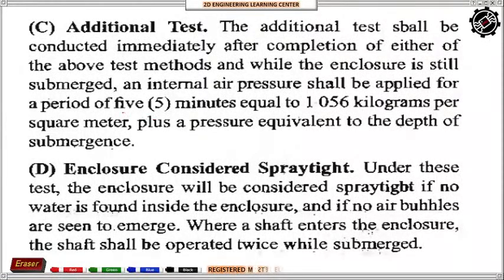The additional test must be done within 5 minutes, subjected to a pressure equal to 1056 kilograms per square meter. Likewise, it also has an enclosure spray tight. Under this test, the enclosure can now be considered as spray tight.